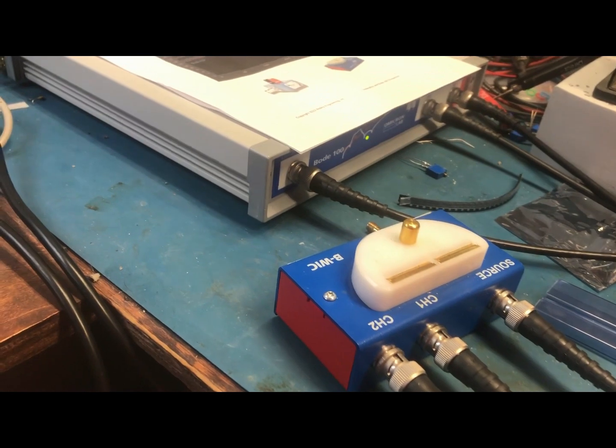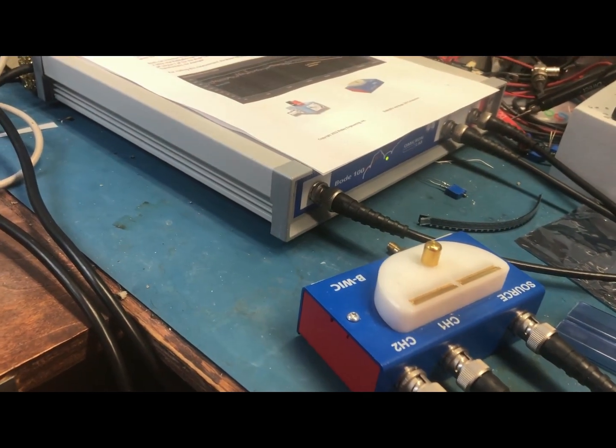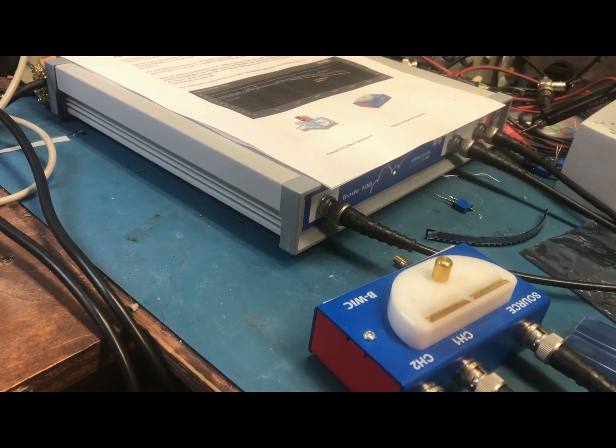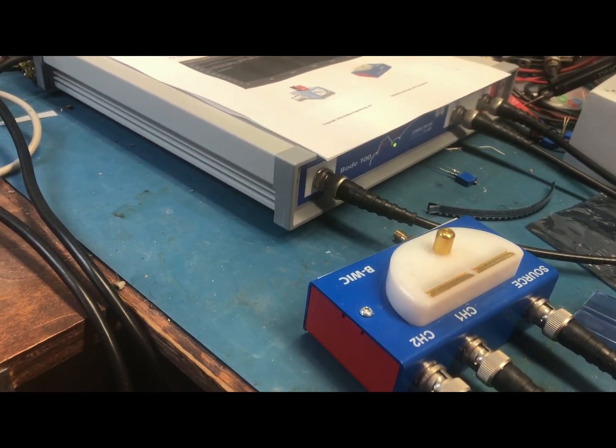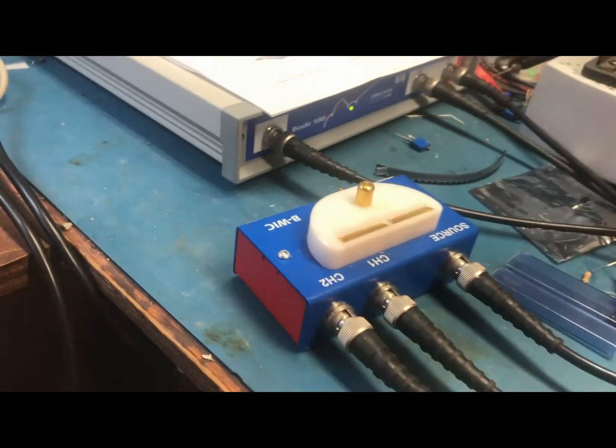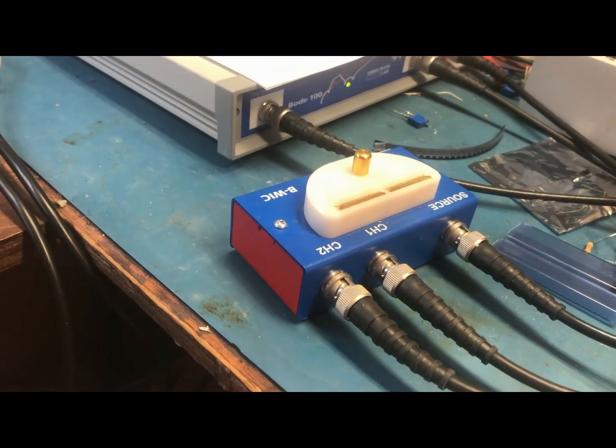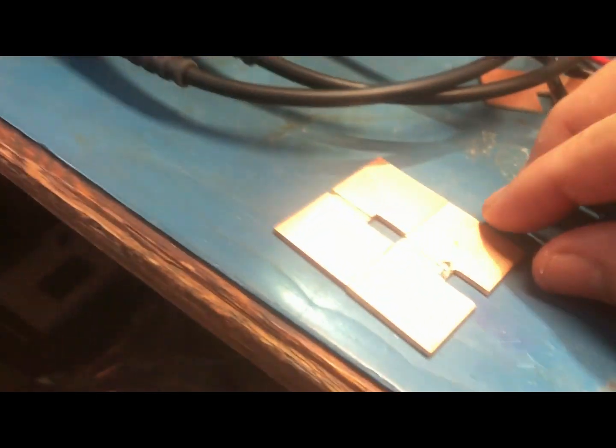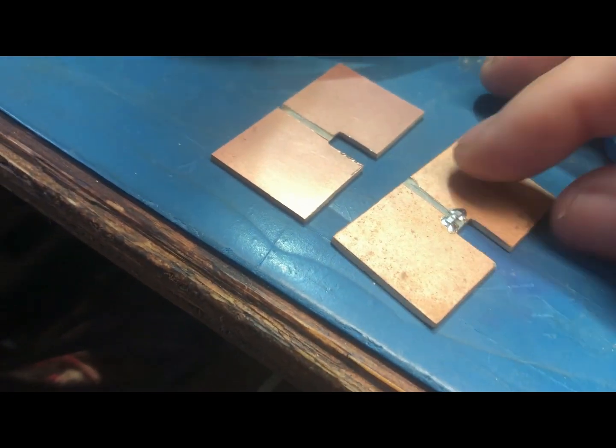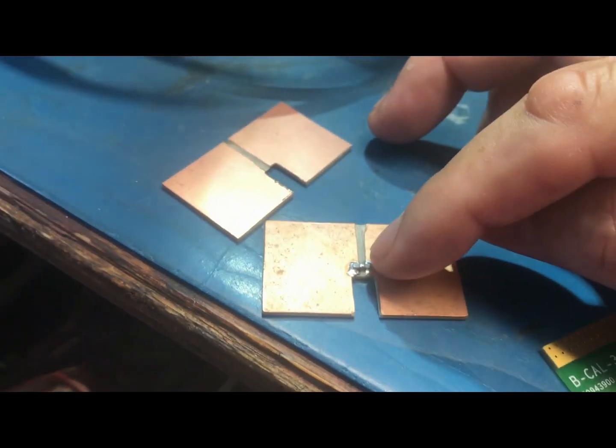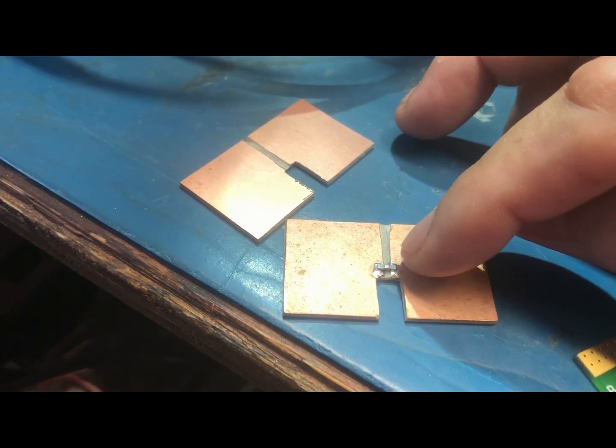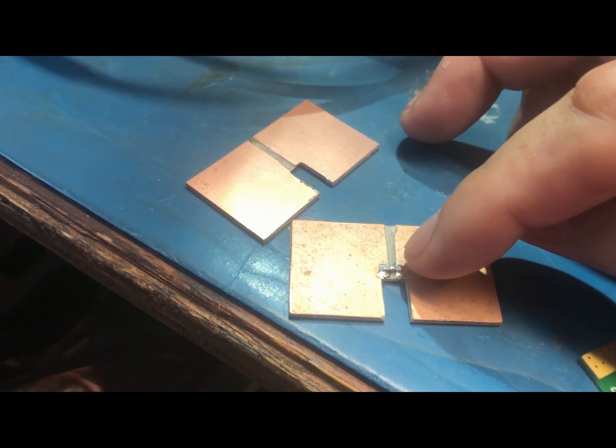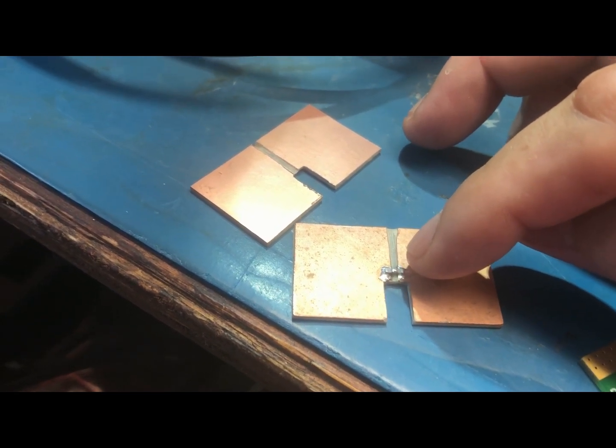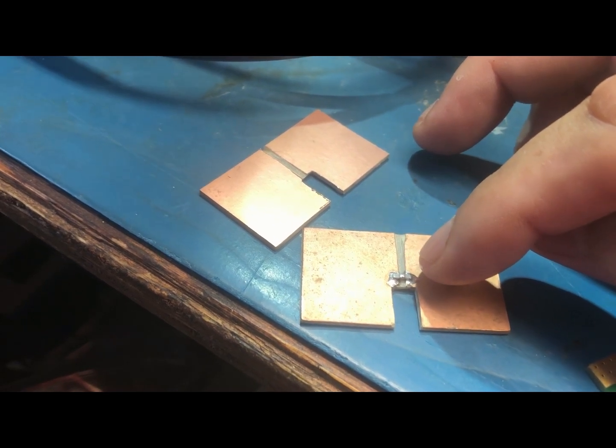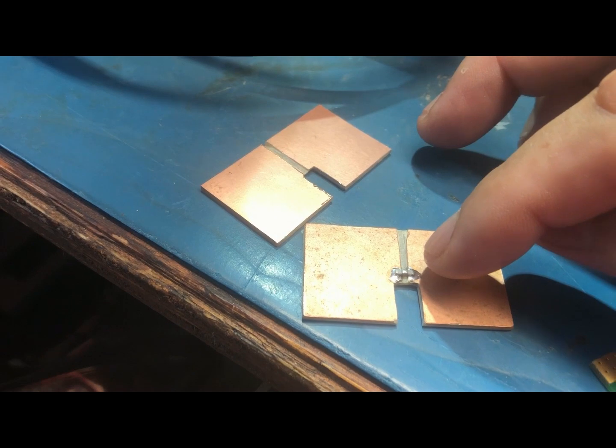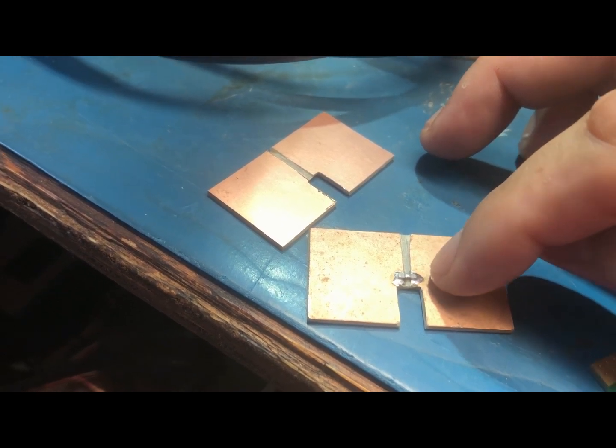And so I'm going to show how to calibrate it. But I also want to do a measurement as well. Because it's not just a matter of measuring the parasitics or calibrating out the parasitics. You want to be able to make a good measurement. So here I have my device that I'm going to measure. These are 2 half picofarads connected in series, so that should total 250 femtofarads, or a quarter of a picofarad.